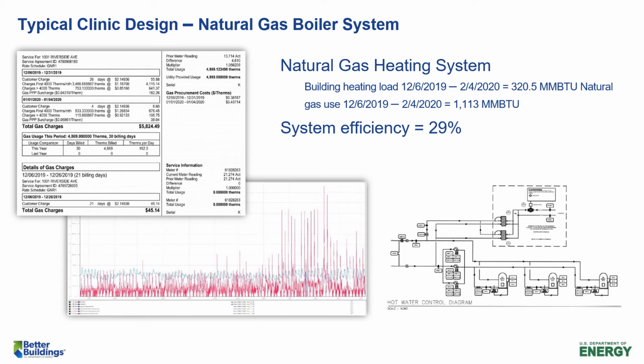Now I'm going to do a little diversion to another building and talk about the energy performance gap. Natural gas is a big recurring theme we've seen in the energy performance gap. I'm not giving you the name of this building, but on paper these are 3 boilers that are 95% efficient, and in our design energy models they're 95% efficient. I'm inclined to believe the boiler manufacturers that these boilers are in fact built for 95% efficiency. But when we put them in buildings, we tend to oversize them and connect them to pumping systems and zone controls that introduce a whole lot of inefficiency.